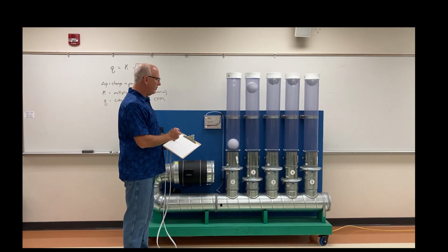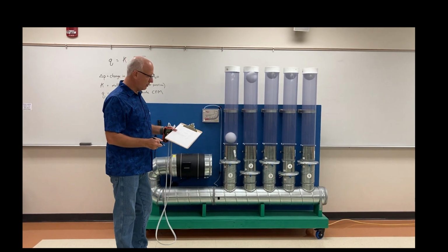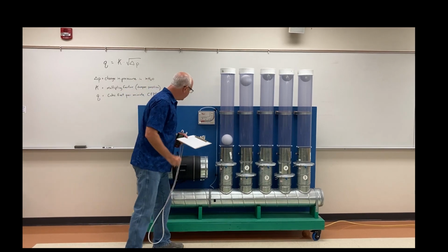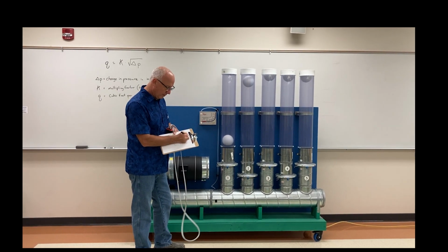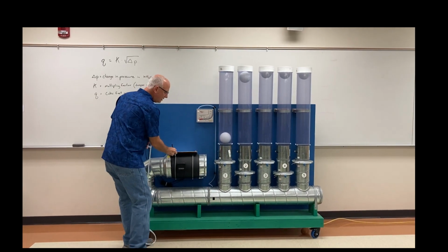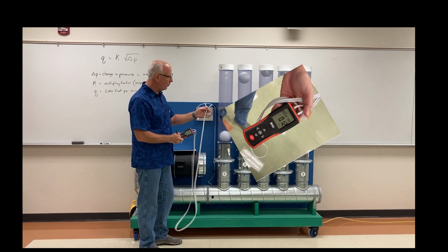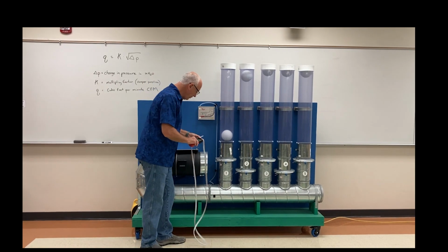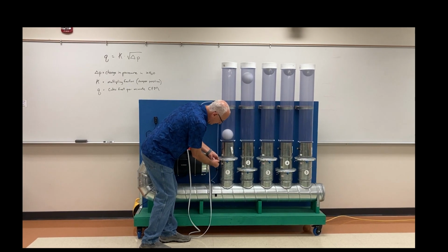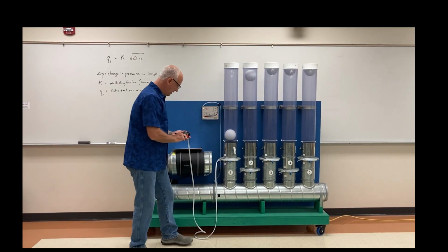Alright, so now that we're getting ready to measure the airflows, I've got a data sheet that we're going to record what the airflows are currently right now. So the static pressure in the system in inches of water is at 0.05 inches of water. And each damper has a high port and a low port. And I have a meter that has a high port and a low port. And I have it set to inches of water. And I simply slide the tubes on and take a reading.